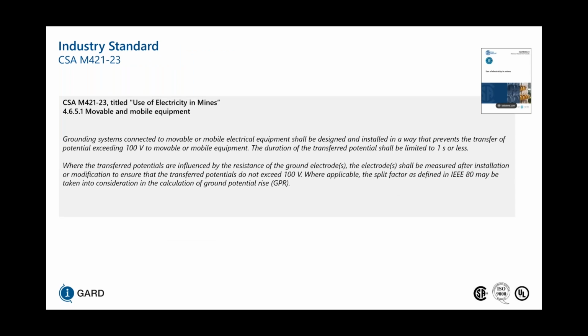Now, if we look at the M421 standard, it says that grounding systems connected to movable or mobile electrical equipment shall be designed and installed in a way that prevents the transfer of potential exceeding 100 volts to movable or mobile equipment. And the duration of that transferred potential shall be limited to 1 second or less. And then in addition to that, when we're doing the installation, we have to measure after to ensure that the transferred potentials do not exceed 100 volts. And where applicable, you would apply the split factor as defined in IEEE 80 into consideration for your ground potential rise calculations.